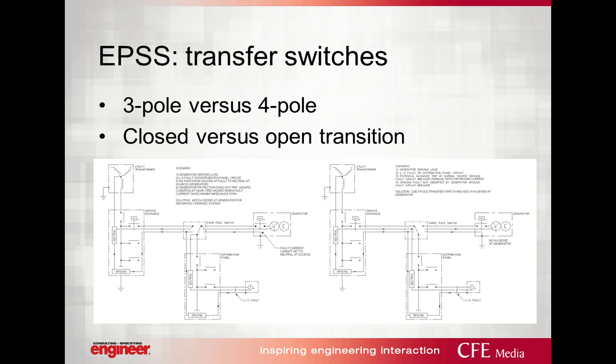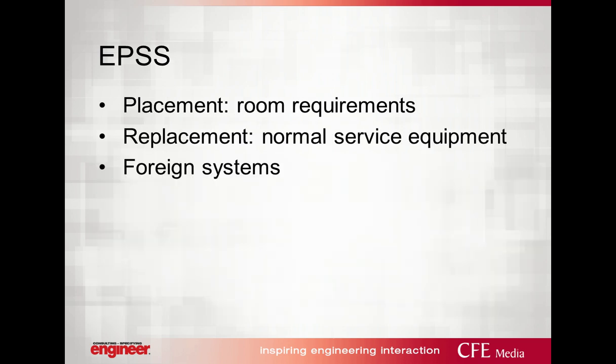Ideally, that's exactly what you'd want to do for most applications, but you're going to run into an issue when you go to upgrade existing facilities. Now, for closed versus open, we want to take into consideration the disruption that we're going to see in an open transition. And we're talking from normal to emergency under test, or emergency back to normal when utilities return. That slight blip can cause failures of building automation system controllers. It can also cause computers to drop out. So you're going to coordinate whether you want open, closed, or maybe even delayed transition for each one of your applications.